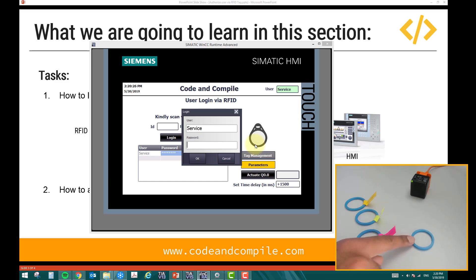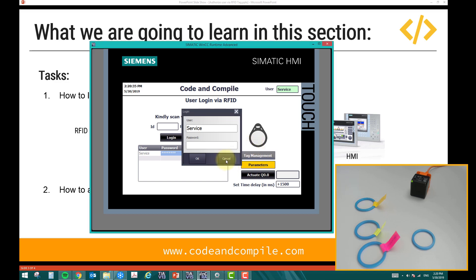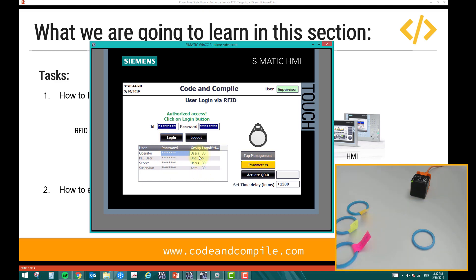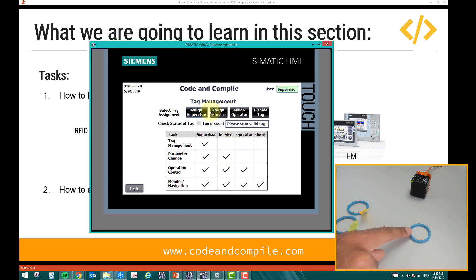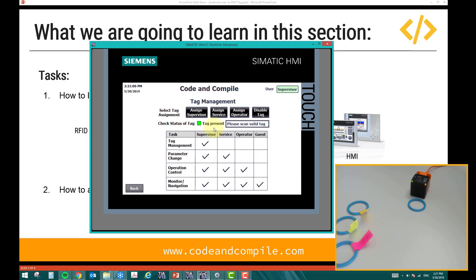Now for tag management — if we have a new tag and want to authorize it as an operator, neither the operator nor the service user can do that; only the supervisor can. I log out and log in as supervisor, then take the tag away. Now the supervisor is logged in and can access tag management. In tag management there is an option to assign a tag — I choose to assign it as 'operator', click 'assign operator', bring the tag near the head, and when the orange light goes off, it is successfully written.